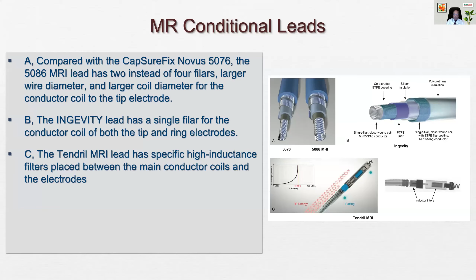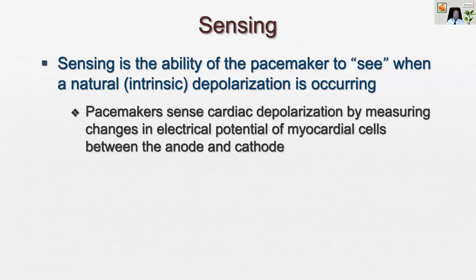Now coming to the functionality, that is sensing. Sensing is the ability of the pacemaker to sense electrical signals when natural depolarization is occurring. And we know that all pacemakers work in demand mode. That means they can sense the patient's activity and inhibit themselves from pacing. So that's very important. And this is another important aspect of intracardiac electrograms. Some of you may be exposed to electrophysiology, but most students are not always exposed to electrophysiology and intracardiac electrograms.